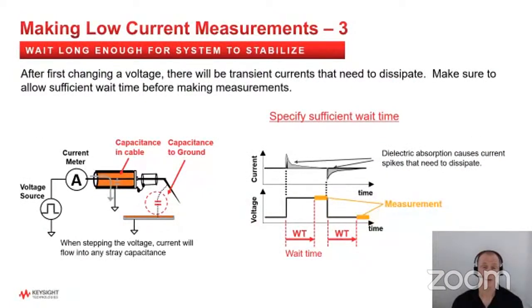Cable capacitance also has an effect on your measurements, especially if you're trying to do a sweep measurement where you want to change the value of whatever you're measuring. As I mentioned, there are parameters. There's a hold time, which is the initial time before you start the measurement, and also the wait time, the time you wait after the voltage changes before starting a measurement. So these are very important parameters. Again, if you have a lot of capacitance in your setup and you're trying to do maybe a sweep measurement and you're not getting good results, try playing around with the hold time and the wait time and see if that will actually improve your measurement results.